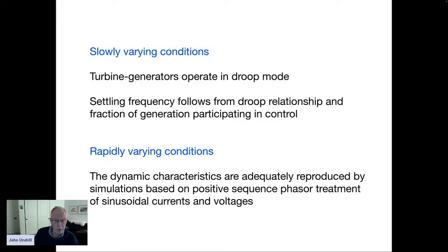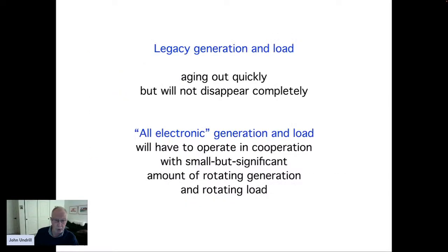Things vary slowly. The generators operating in droop mode do what's required. They do it autonomously. They do it naturally. They're not dependent on high bandwidth communications. When things are moving slowly, the droop equation is a pretty good description. So there's a summary of the legacy of the system we're aging out.